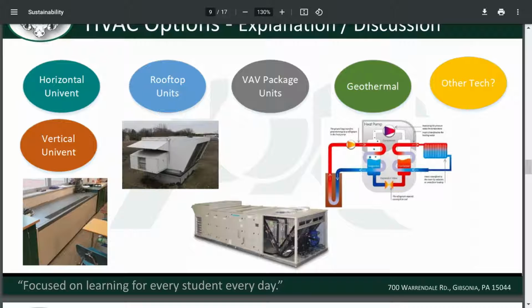Then there's geothermal—that's the option on the expensive side but more efficient, which people into sustainability like to push. It's expensive; we'd have to drill down into the earth and put in little wells with coils, which replaces the big boiler. The ground temperature is about 55 degrees, so it takes the edge off the heat exchange. You'd still need a heat pump and some cooling system, but it wouldn't need to be as big because you're using the earth to help out. But those are very expensive.